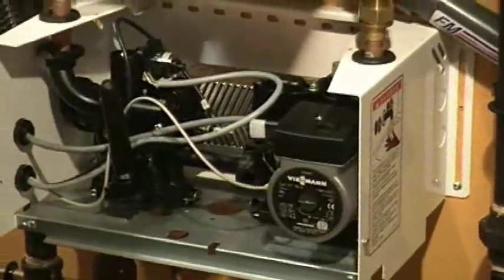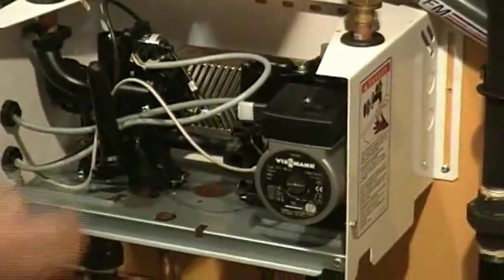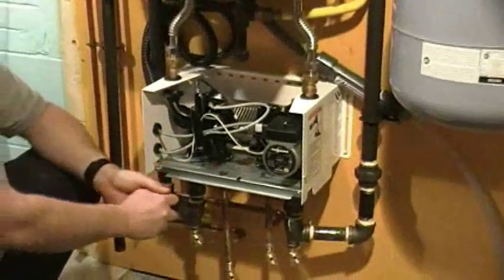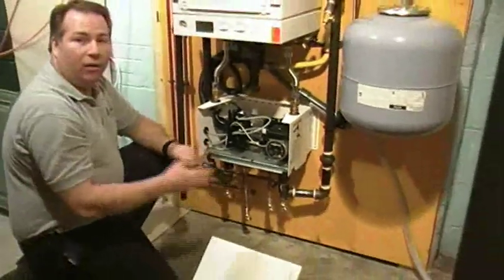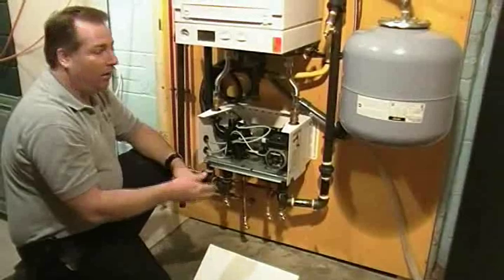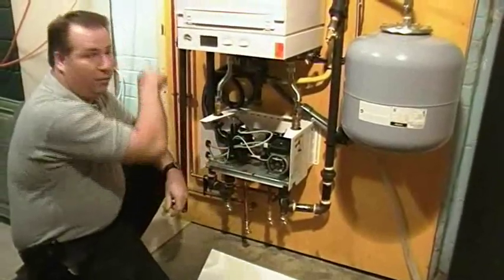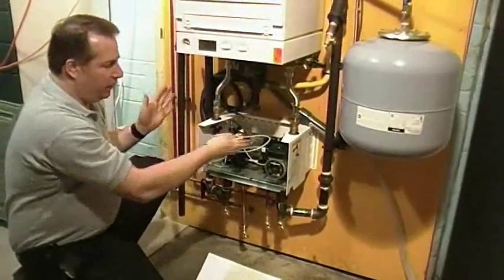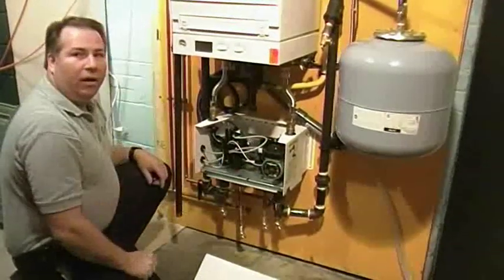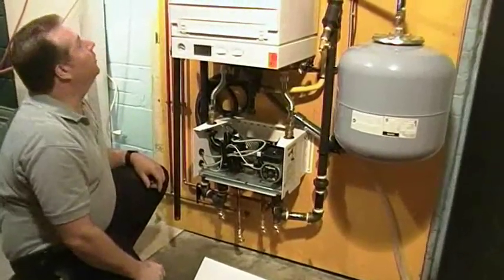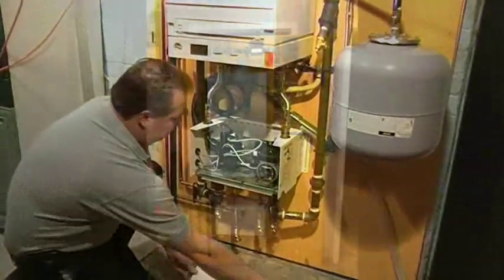And basically what it does is when domestic is needed, it diverts water through the heat exchanger. When domestic is no longer needed and house heating is needed, it brings on the water to flow through the primary loop. This takes up very little room. This was on a 4-foot sheet of plywood about 7 foot tall.